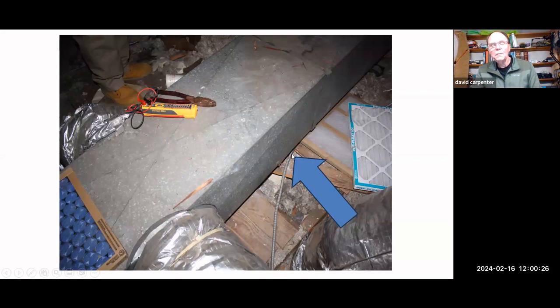This was bad thinking on somebody's part. You should never lay ductwork on top of a cable, because the ductwork moves constantly and has vibration in it. In fact, there are vibration pieces installed to keep the ductwork together. Doing this gives a good chance of pinching the cable, and eventually the cable won't take that movement. It was never made for that. This is a major violation. It should have been covered.